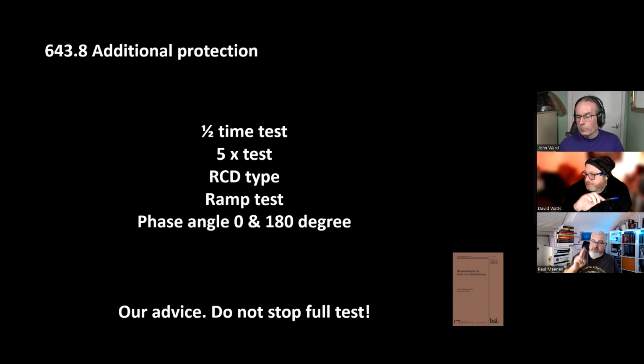So this is a minimum, and this is where we need to stop panicking and go, the regs are a minimum guidance note. I feel sorry for anyone that does a 1 times test at the RCD, because all you're doing is effectively mimicking part of the factory performance test. Now, I've noted over the years that I think it was the NIC who said just test at the terminals because of the capacitive effect of the circuit. Wrong. I know, Dave, there is an argument to be had that we should trust RCDs like we do MCBs. Wrong, because MCBs don't get blinded like RCDs. So that's my personal professional opinion.